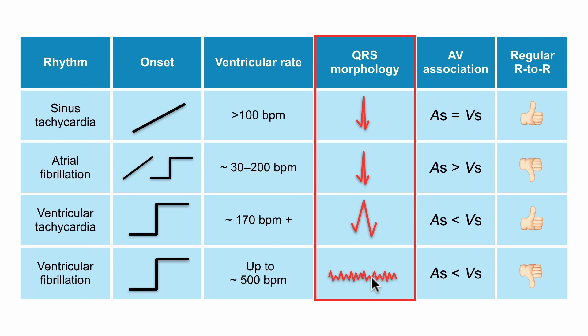The QRS discriminator looks to recognize when the QRS has become so different that a ventricular arrhythmia is assumed.